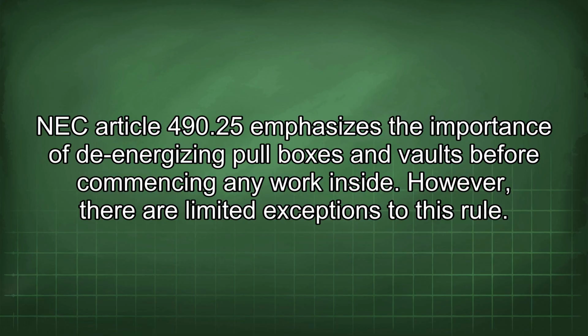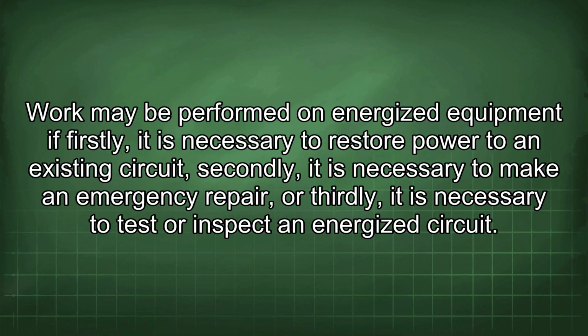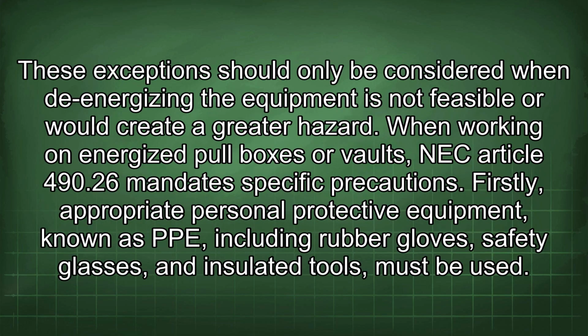NEC Article 490.25 emphasizes the importance of de-energizing pull boxes and vaults before commencing any work inside. However, there are limited exceptions to this rule. Work may be performed on energized equipment if, firstly, it is necessary to restore power to an existing circuit, secondly, it is necessary to make an emergency repair, or thirdly, it is necessary to test or inspect an energized circuit. These exceptions should only be considered when de-energizing the equipment is not feasible or would create a greater hazard.